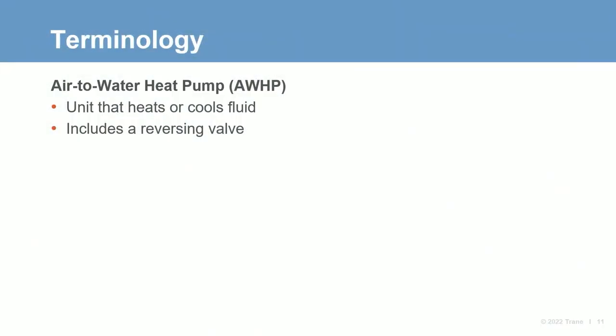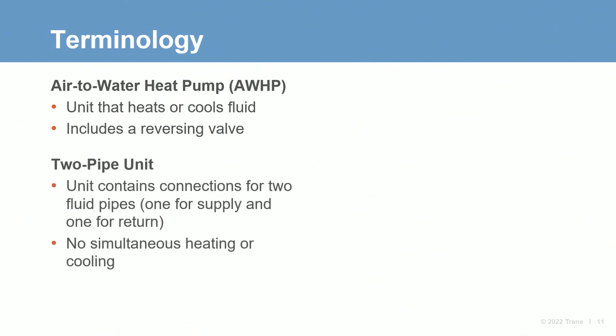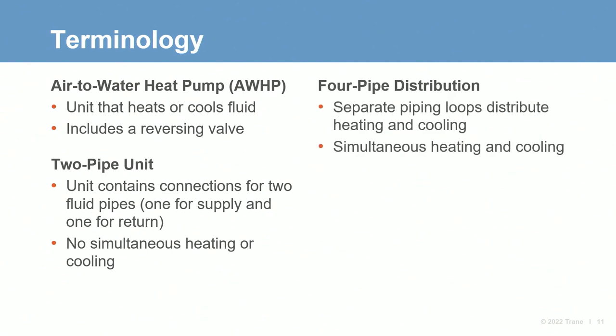Now, before we get into the electrified heating system details, let's take a moment to get grounded in some of the relevant terminology. First, air-to-water heat pumps are units that can heat or cool fluids, and they may include a reversing valve in the refrigeration circuit. They also may include more than one refrigeration circuit. Two-pipe units have one pipe for fluid supply and one pipe for fluid return. These units can heat or cool fluid, but not simultaneously. Four-pipe distribution systems use separate piping loops to distribute heating and cooling fluids and can do so simultaneously in the building. Now, much of our discussion will involve two-pipe units in the chiller heater plant, along with four-pipe distribution systems.